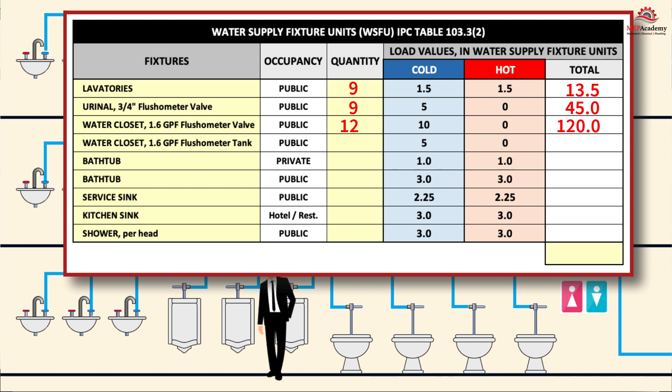Add up the WSFUs for all fixtures in the building to get the total WSFUs, including totals for each branch and riser. Note that water flow demands for cooling towers, RO systems, process equipment, or landscaping have not been considered here — the plumbing engineer will need to work with other trades to determine their water needs. In our example, we have 13.5 WSFUs for lavatories, 45 for urinals, and 120 for water closets, for a total of 178.5 fixture units.